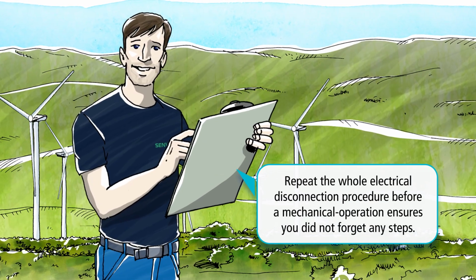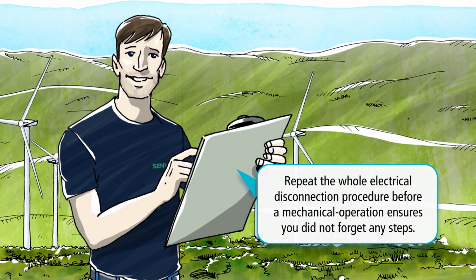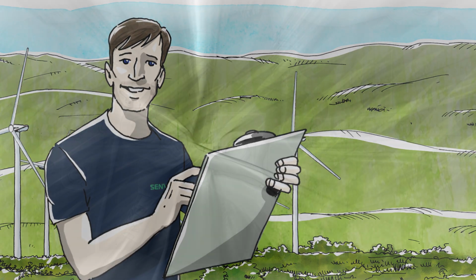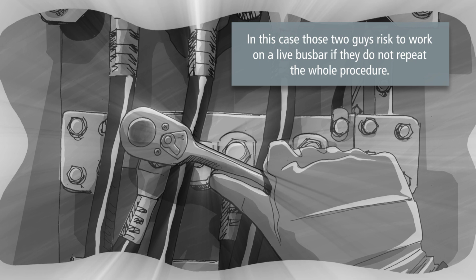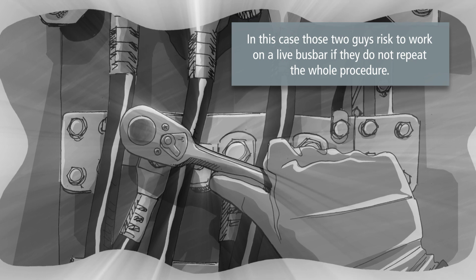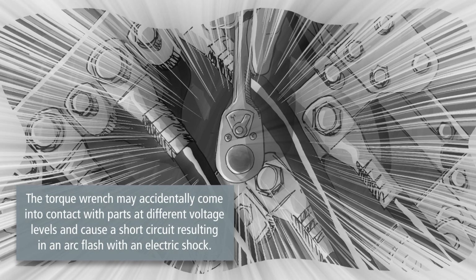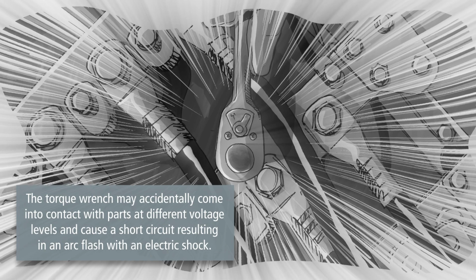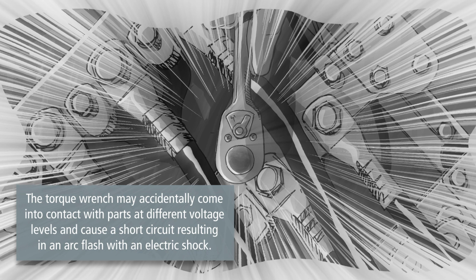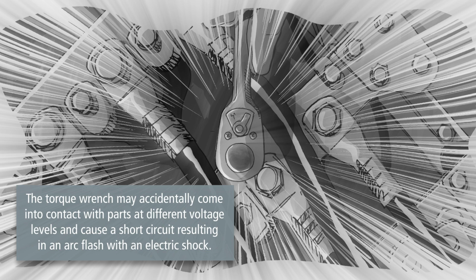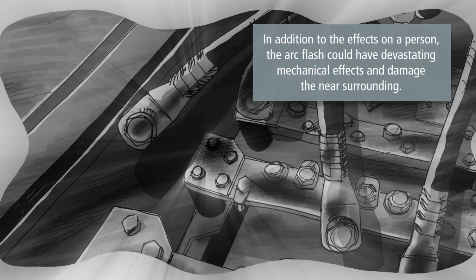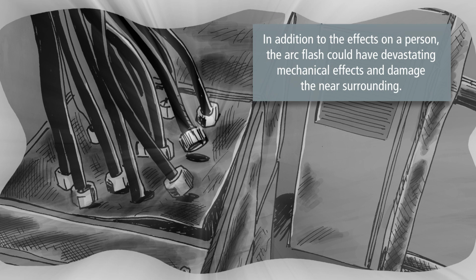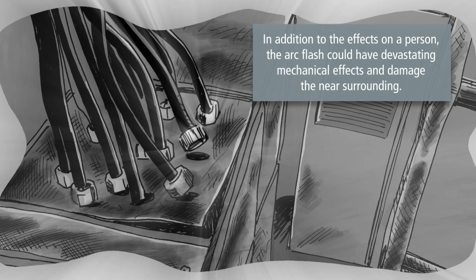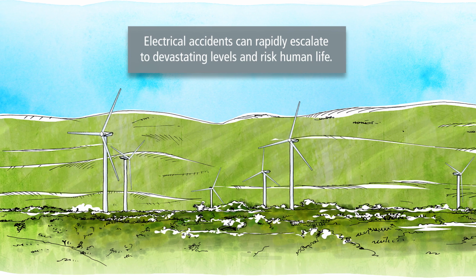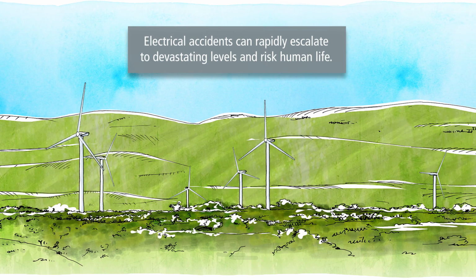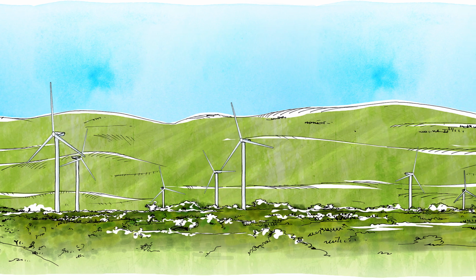Repeating the whole electrical disconnection procedure before a mechanical operation ensures you did not forget any steps. In this case, those two guys risk working on a live bus bar if they do not repeat the whole procedure. The torque wrench may accidentally come into contact with parts at different voltage levels and cause a short circuit resulting in an arc flash with an electric shock. In addition to the effect on a person, the arc flash could have devastating mechanical effects and damage the near surrounding. Remember, electrical accidents can rapidly escalate to devastating levels and risk human life.